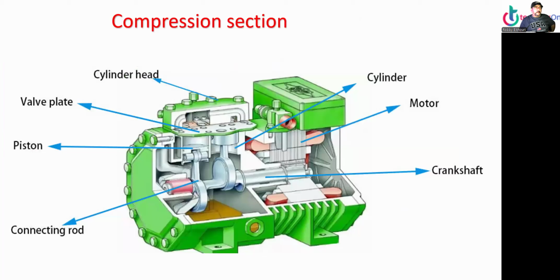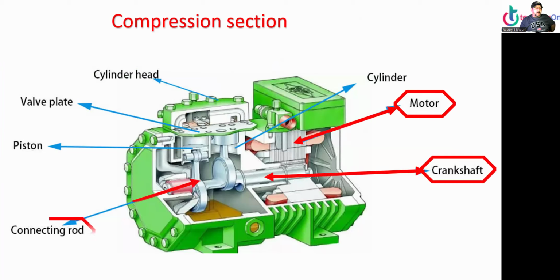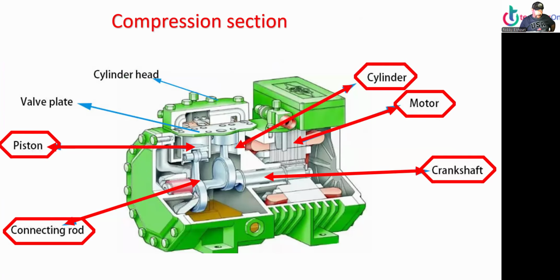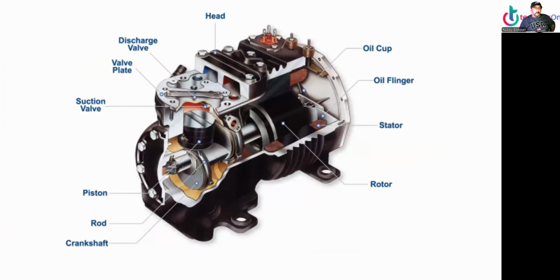Compressor section. All right, so we have the motor here. The motor drives the crankshaft. The crankshaft moves the connecting rod. The connecting rods will move the pistons up and down. The pistons go inside the cylinder. The pistons and cylinder pump into the valve plate, and all this is in the cylinder head.